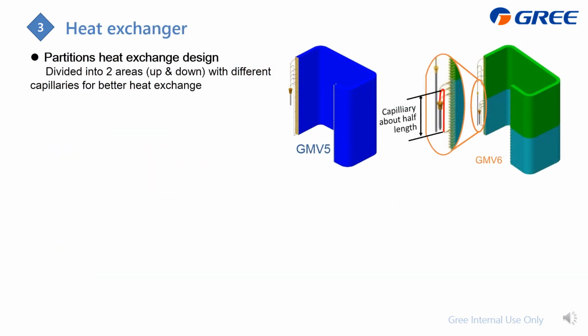About the heat exchanger, compared with GMV5, GMV6 improve or upgrade lots of the points. First is the partition heat exchanger design. For the GMV5, this is the outdoor heat exchanger. You can find that this is the outdoor distributor, and for this whole outdoor heat exchanger, it is just one. And for GMV6, we divide it into these two partitions. And the benefit, just compared with GMV5, it is that this is the distributor when you need to distribute the liquid refrigerant in heating from here to the furthest passes.